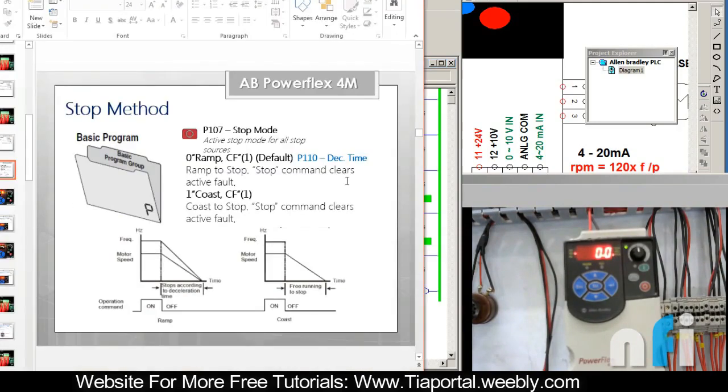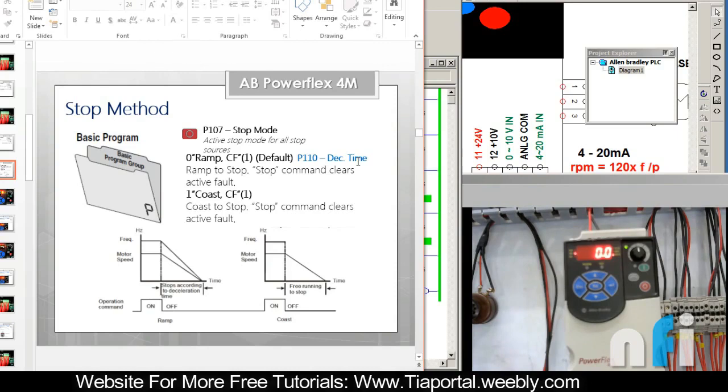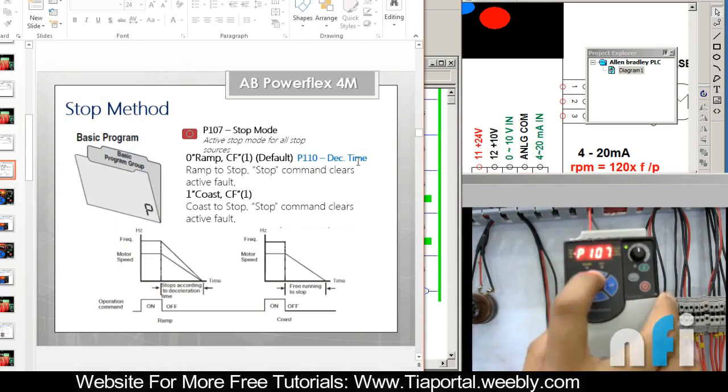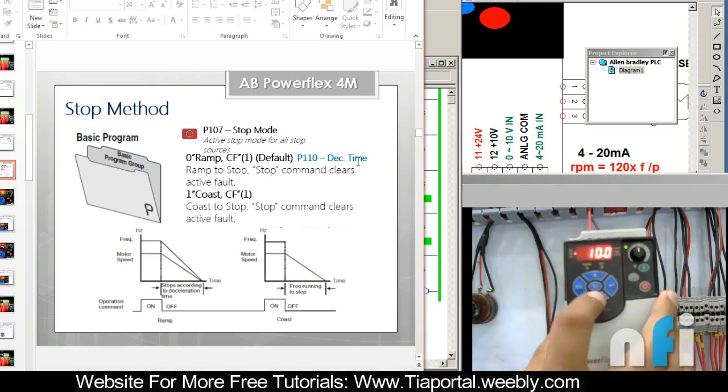By default, that is a ramp stop. It's taking time to stop and there is some parameter which is associated with the ramp stop. It's P110, this is the deceleration time. You can change that time. If you want a quick ramp you can reduce this time to minimum 0.1. Right now my default is at maximum which is 10 seconds, 10 seconds with respect to 50 hertz.